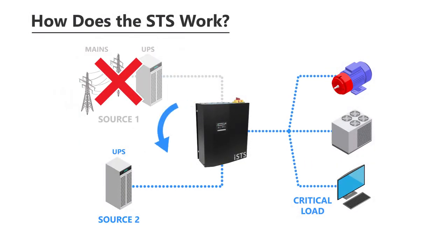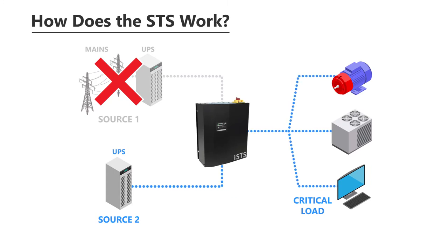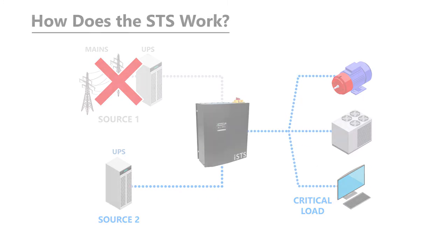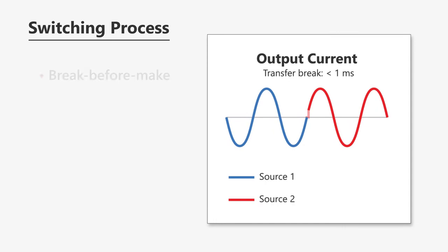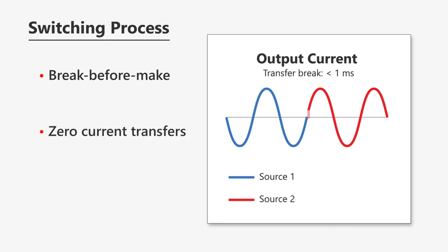The STS automatically and seamlessly switches to the alternate power source upon detecting a fault or failure. The switching process is break-before-make to avoid paralleling power sources. Transfers are performed at zero current to eliminate any impact on the load. Solid-state switching components enable rapid transfers with minimal break time.